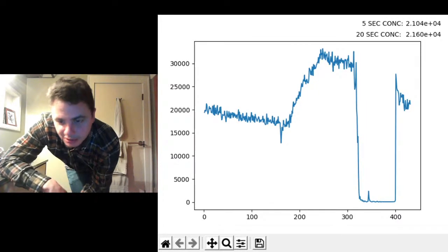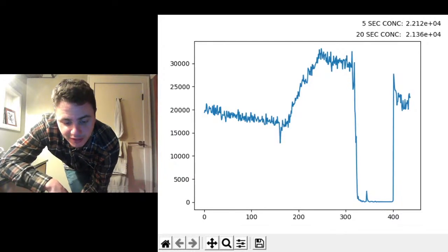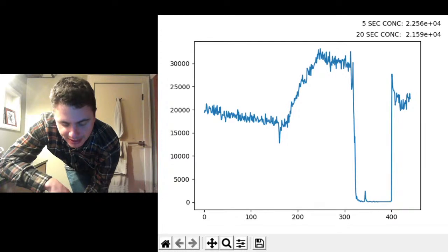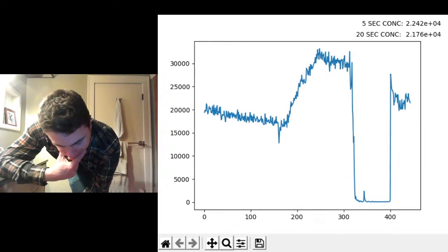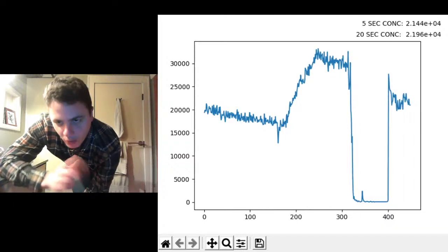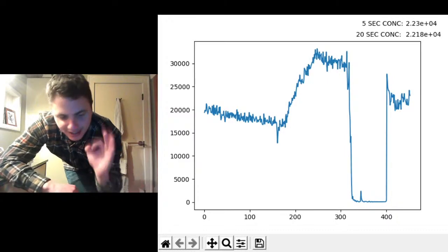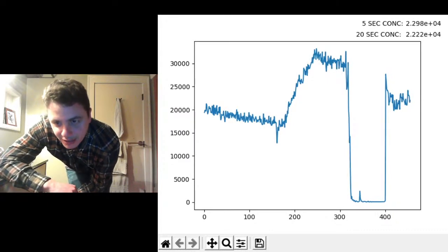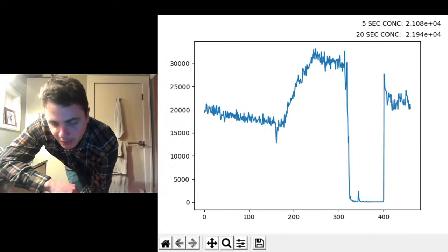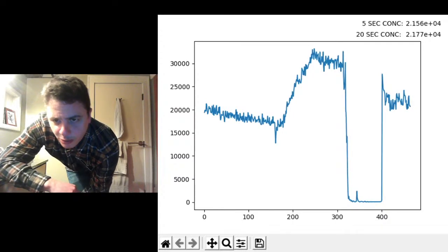So in my general guesstimate, now again, I'm not an epidemiologist and I haven't been watching the COVID situation enough to know exactly what the term is for the exhaled infectious rate, the quanta rate. If you're at 30 minutes or less, in the mid 90s plus, I think you're pretty much money. That's going to be a significant improvement for a grocery shop. So 90 plus is kind of the target I'm going to recommend. If you're going to be around COVID positive people for 8 hours, you're going to need something more protective, especially in close proximity. So hopefully that answers your question, Walter.